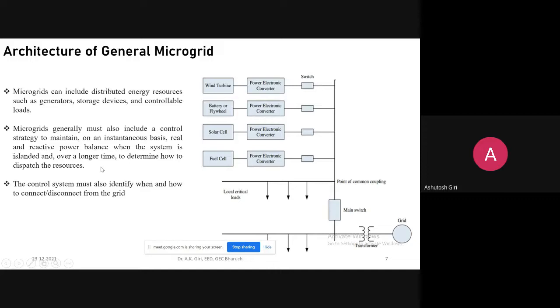Reactive power balance must be maintained when the system is islanded, and over a longer period it must be determined how to dispatch the resources. This point is known as the point of common coupling, PCC, where critical loads are connected. This is the main switch through which we connect to the grid. In my work, basically this grid connection part is missing; in this presentation we will discuss only the islanded microgrid, which is not connected to any big network.